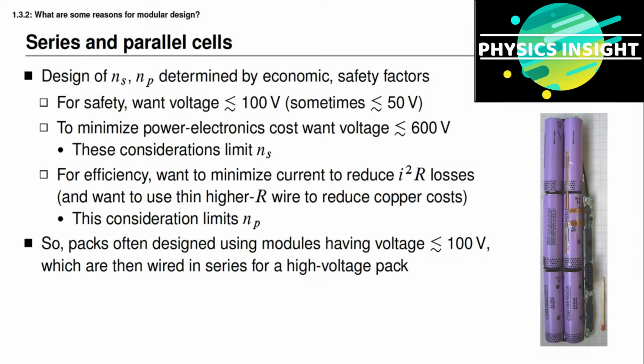A very common solution is to build battery packs from smaller modules of cells. Each module has a DC voltage less than approximately 100 volts in order to maintain safety if a technician is opening the module for diagnostics or repair. Then you take these modules with individual voltages less than 100 volts and wire them in series to make a higher voltage battery pack.